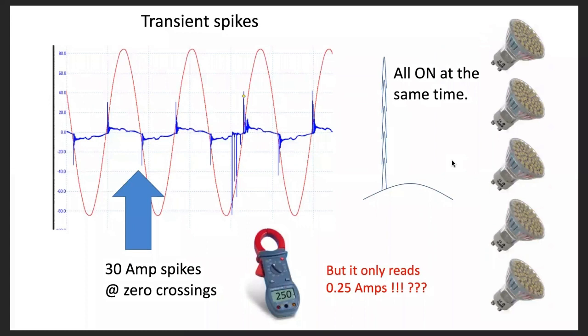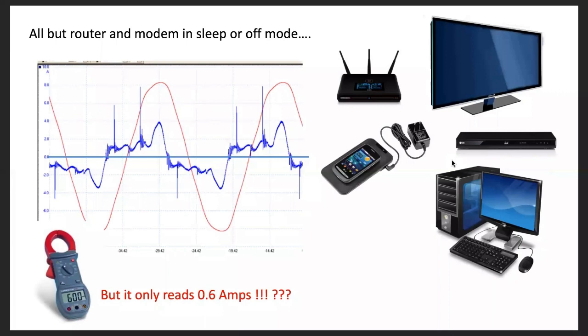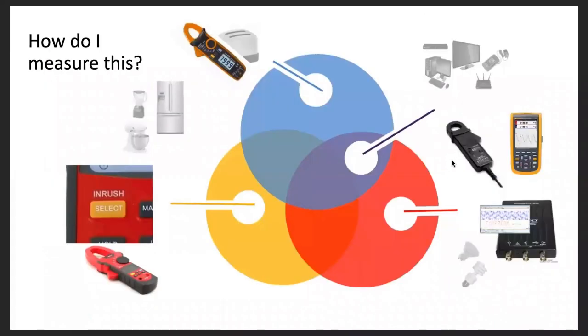So measuring those loads is really important. Can't stress that enough. And the type of equipment that you use to measure those loads is really important too, because you might not always see it. You definitely won't see it with a standard RMS ammeter, especially these transients as shown here. And again, there may be quite an effect on the voltage waveform based on the types of loads that you may not be able to measure with the standard ammeter. So how would you measure those things? Backup loads planning is a big part of installing a battery system, the Evolve especially.